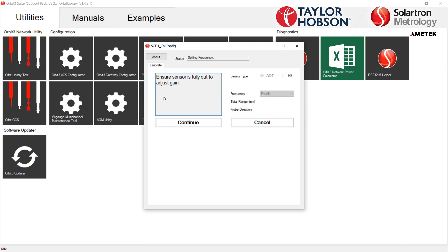Now have the sensor fully out or fully in, and then set the sensor type, LVDT or half bridge. Then after you click Continue, you will want to choose the frequency. For a standard Solartron probe, the frequency is 5K.